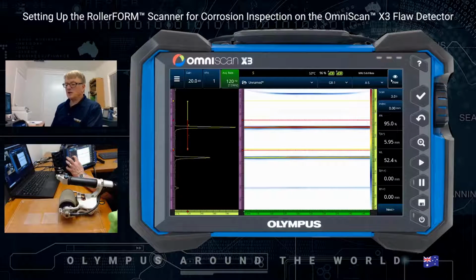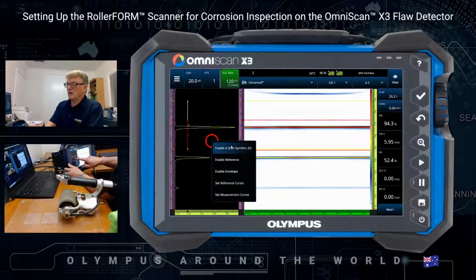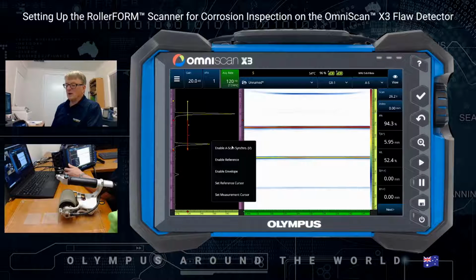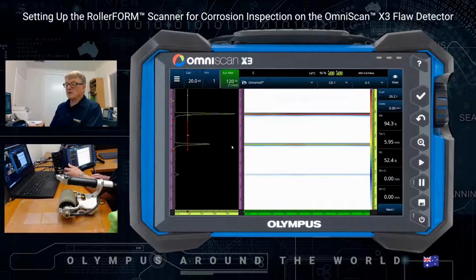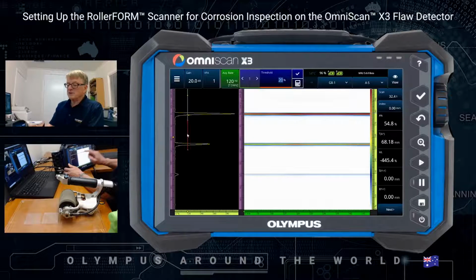Okay, so here you see there's an interface echo and a back wall echo and then a very small second back wall echo. At the interface echo, that could be the echo from a hydroform or a flexiform where it's material, the same with the RollerFORM, or it could be the edge of the end of the wedge. So this can work for hard wedges as well. And what we do is we press and hold, enable the A-scan synchro. So what we're doing here is we're synchronizing everything to the interface echo.